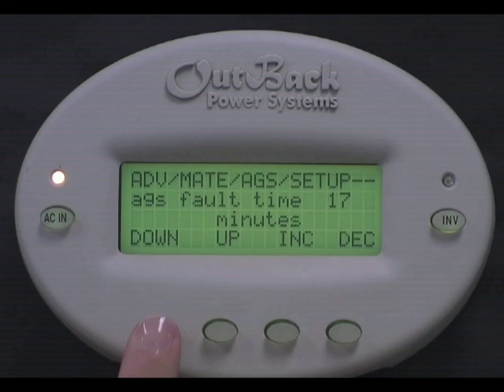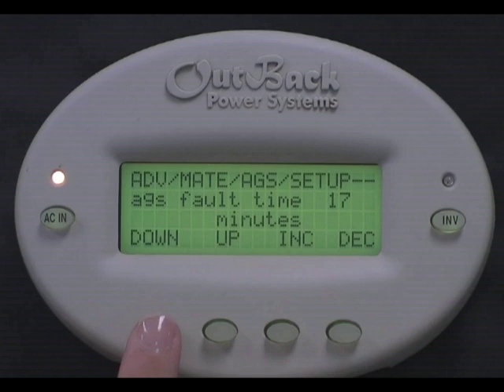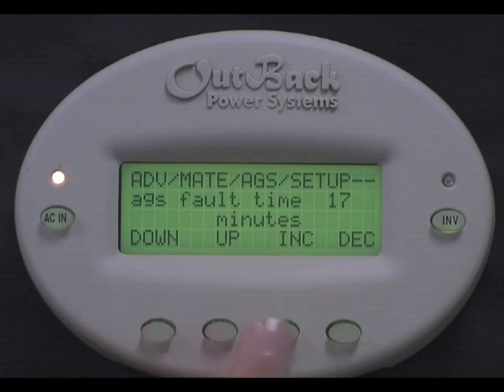AGS Fault Time. 17 minutes is a good number to leave this at. This is the amount of time allowed between the inverter telling the generator to turn on and the system not sensing AC power. If after 17 minutes the system does not sense AC power from the generator, your system will display a fault. You can change this to be anywhere from 6 to 30 minutes.